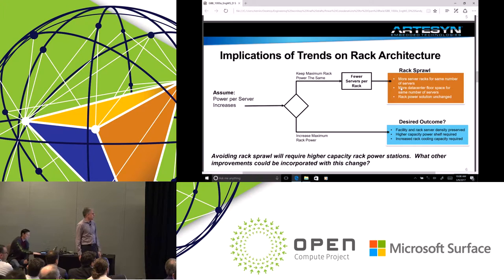The bottom option is you increase the rack power, but now you've got cooling problems to deal with and additional rack power density challenges. That might not work for people trying to keep free air cooling and no heat exchangers within their system. So you can see this touches not just the power within the rack, but very quickly impacts the operational models of the data center, right? And that's why I think it's exciting to talk about this in this forum.